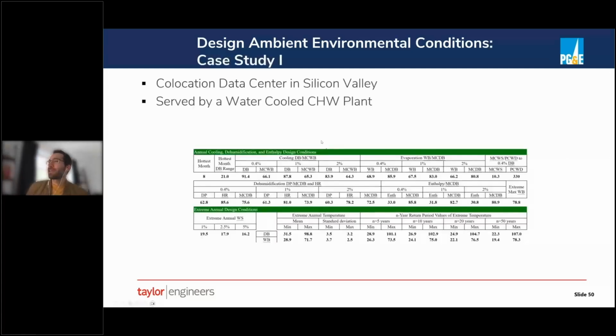So let's start with a case study to show you what not to do. This was actually a colocation data center that I worked on in Silicon Valley about 7 years ago at this point. This particular facility was served by a water-cooled chilled water plant. So anytime you have a water-cooled chilled water plant, the design ambient wet bulb condition is particularly important because it drives the capacity of the cooling towers and whether the cooling towers can supply condenser water at a temperature that's sufficient for the water-cooled chiller.